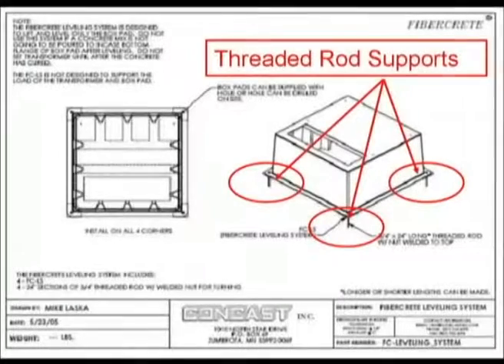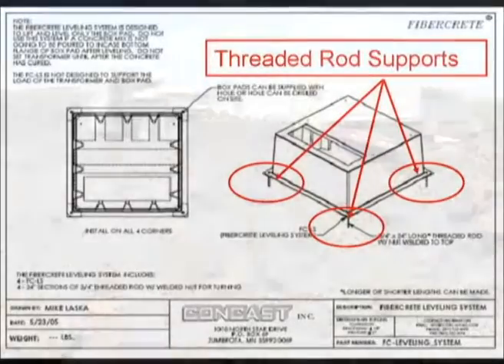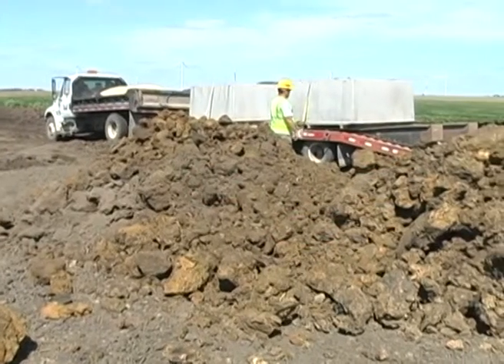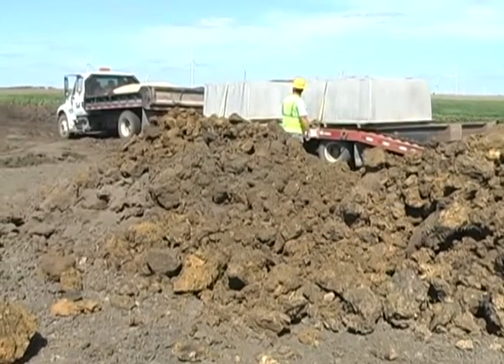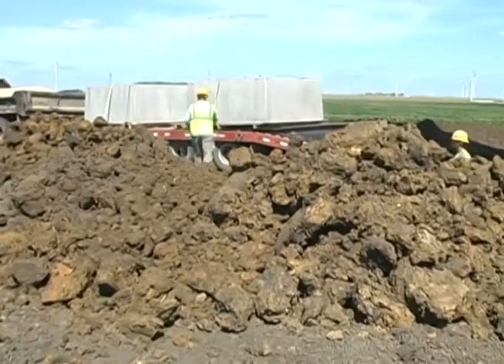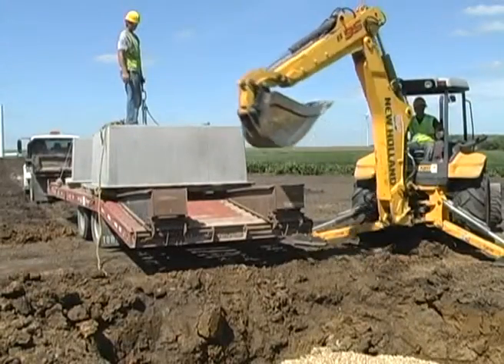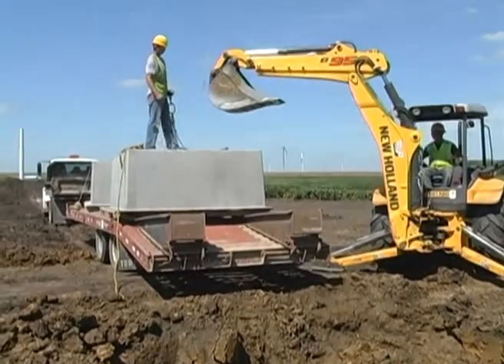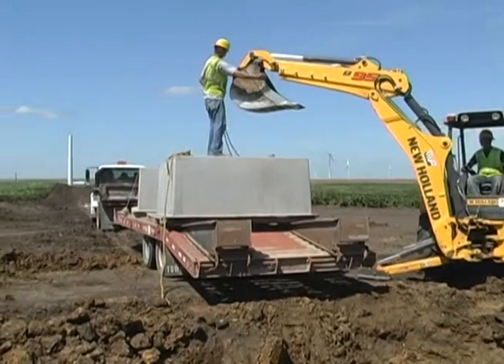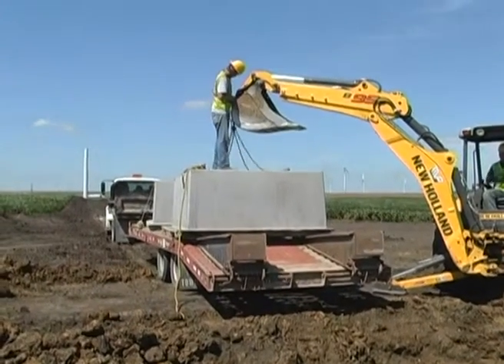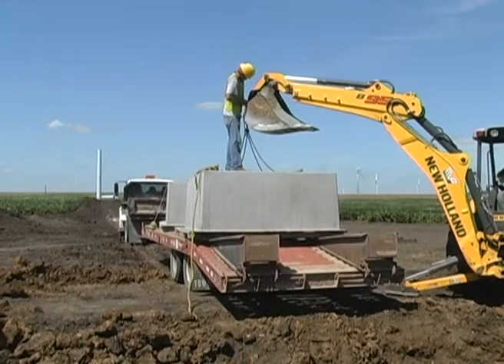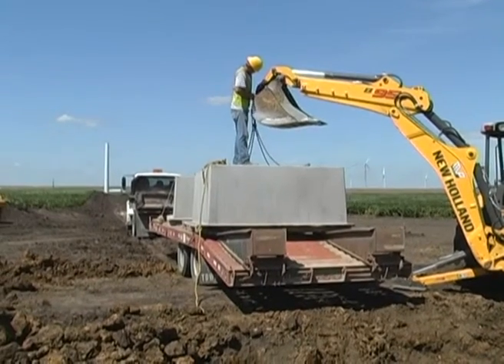Another leveling method that can be used is the incorporation of strut and threaded rod which supports the box pad from the bottom corner. A concrete slurry is then poured under and around the bottom flange. Once the base material is leveled throughout, the large box pad is picked from the trailer. Lifting bolts are screwed in the precast threaded lead inserts in the top face of the box pad, which are then used to attach to the lifting rigging.